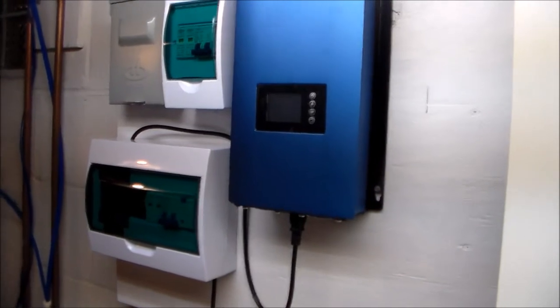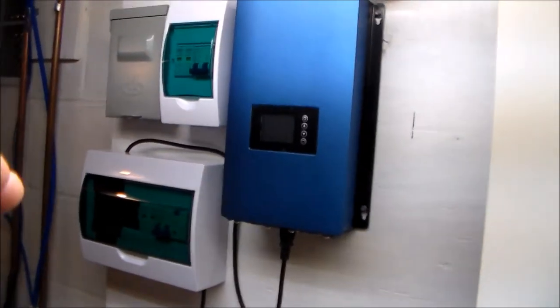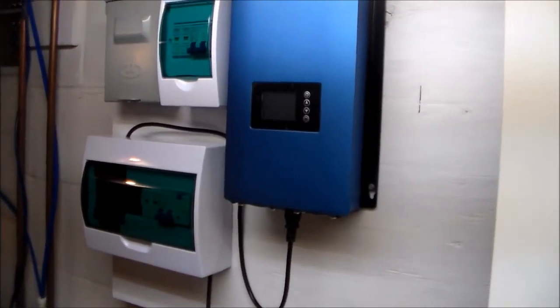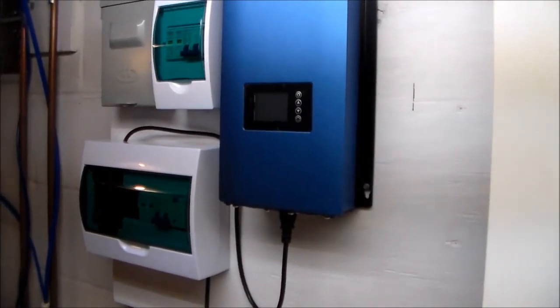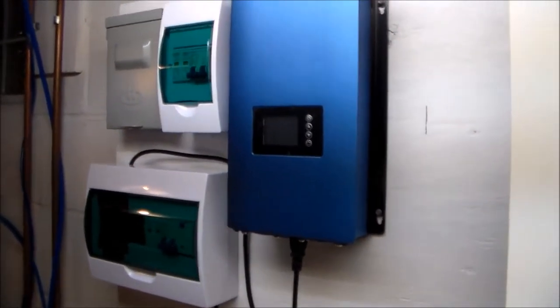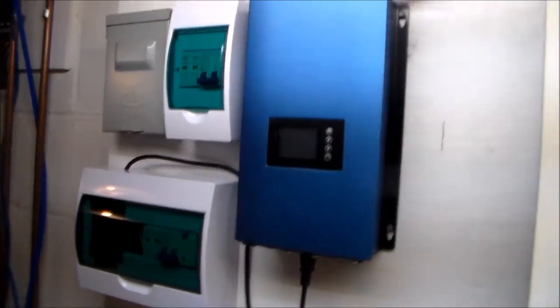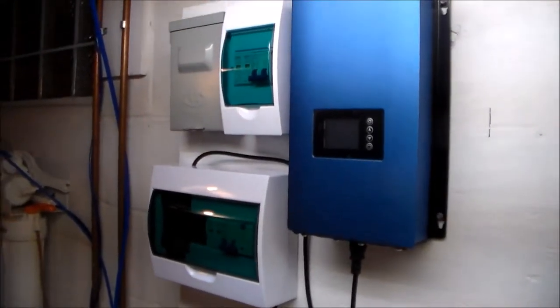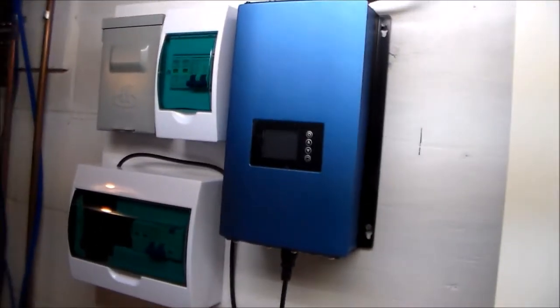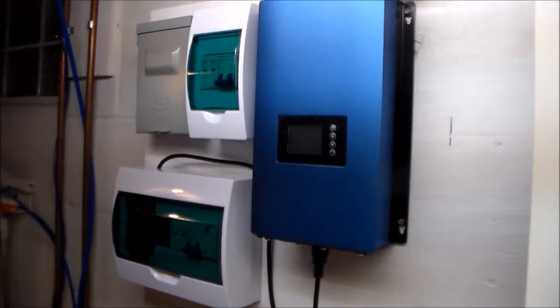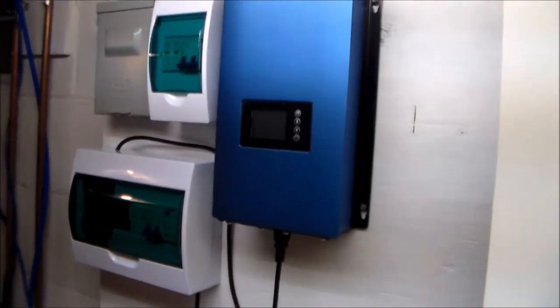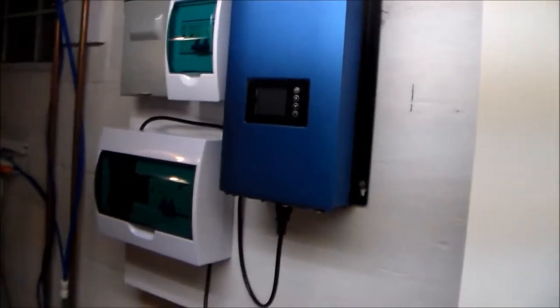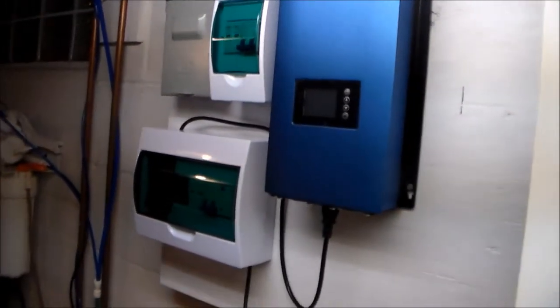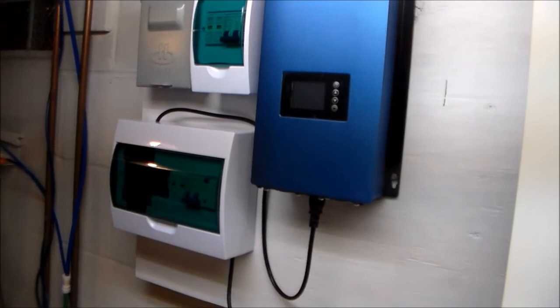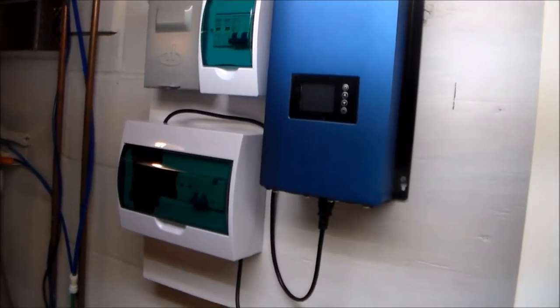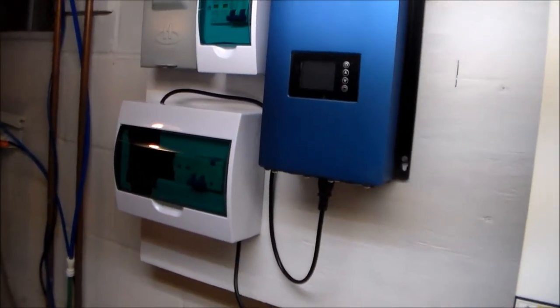So typically you'll want to raise your voltage as high as possible, since you can use smaller cable sizes, and because cable is one of the most expensive parts, especially if you're running a long distance, you want things to run as efficiently as possible and as cheaply as possible when you're buying the cable. So if we wanted to go the most efficient method, we would connect all 4 of those panels in series.